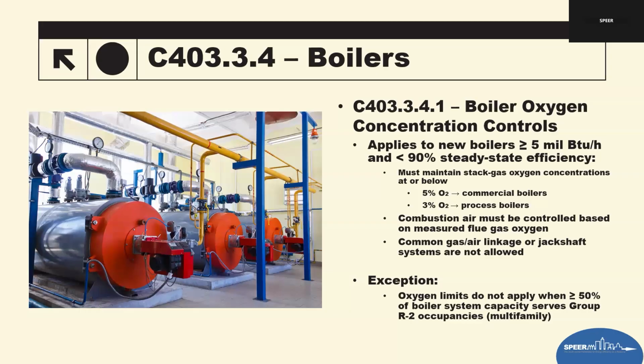So, plan review and inspection tips. When reviewing plans or performing inspections, always start by identifying the boiler size. That input capacity is going to determine what happens next.